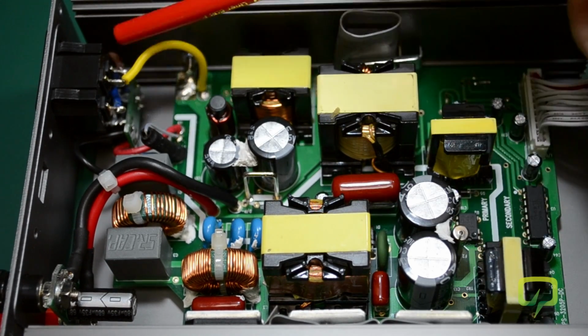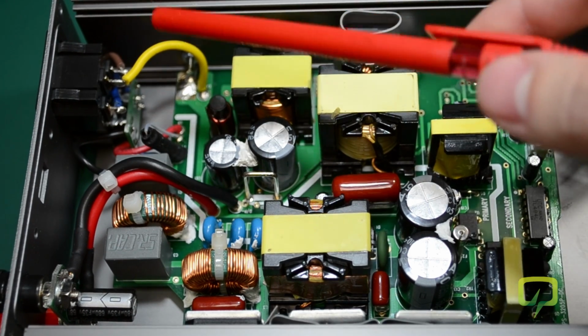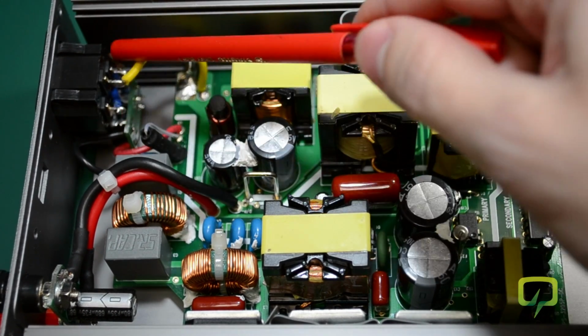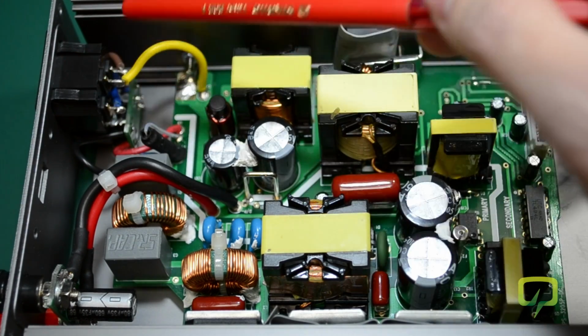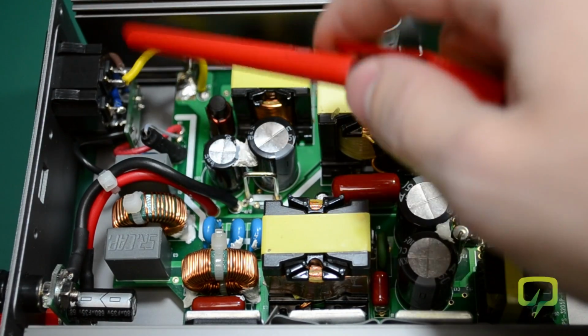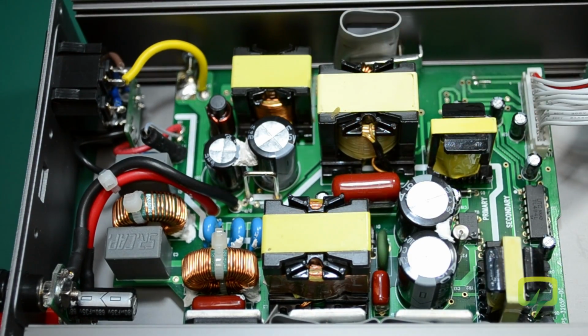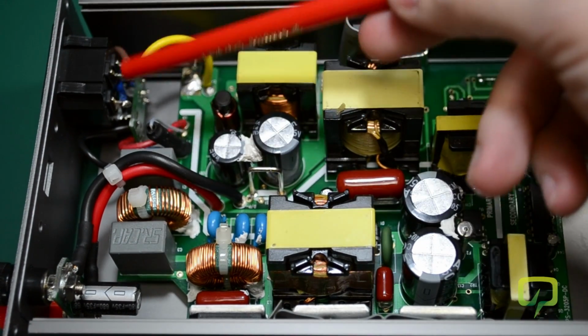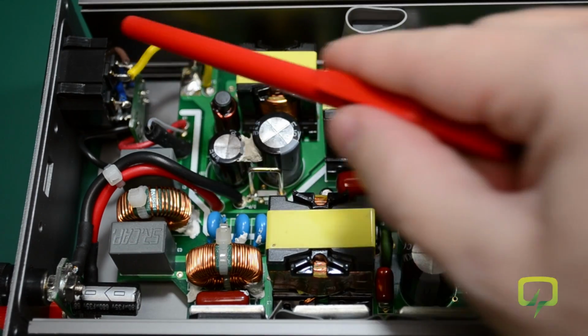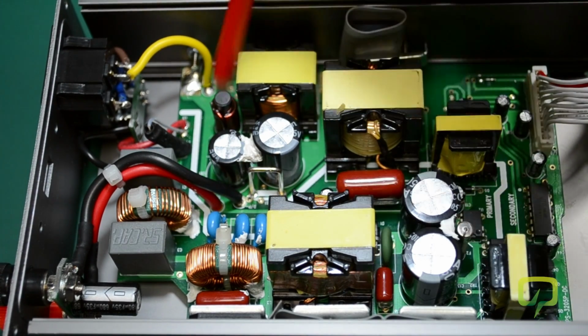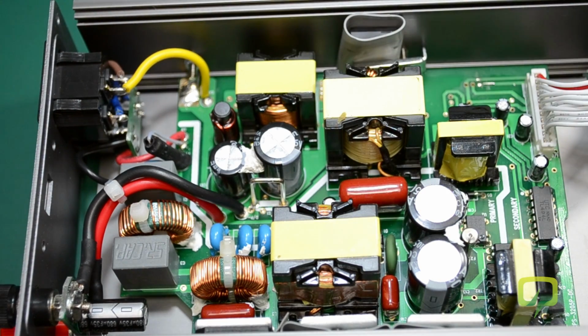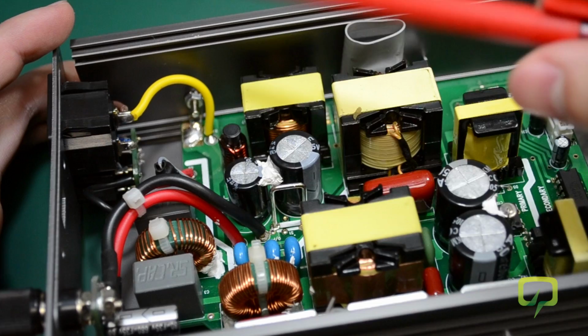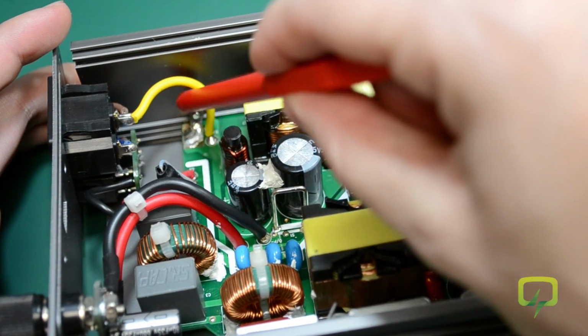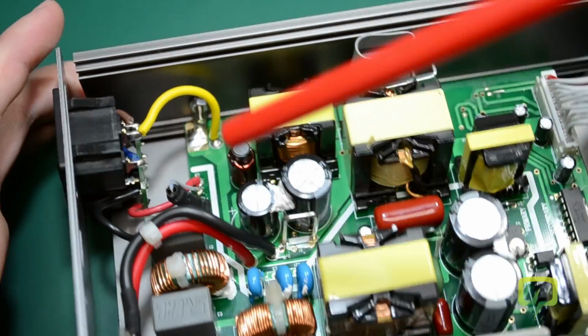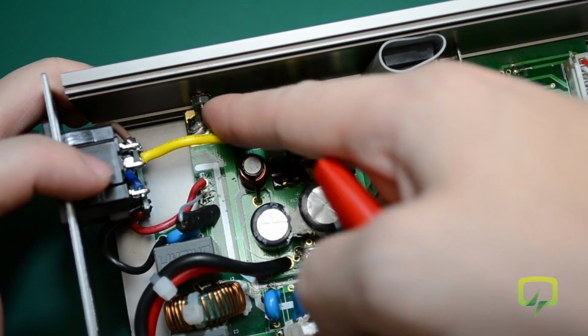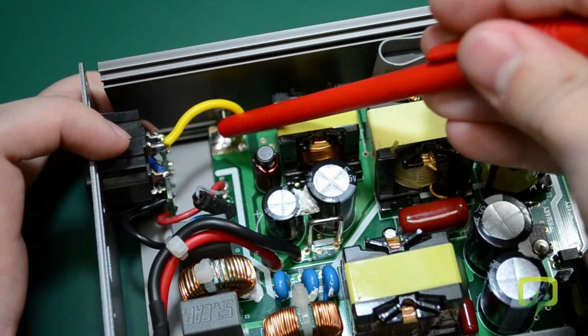Now, starting from the AC input of this power supply, I already see something I don't like. There is no heat shrink on the AC input terminals of the IEC mains socket. It is generally desirable to heat shrink these input terminals to improve the safety of the power supply, but in this case we have no isolation on the input terminals. Moving forward, the earth lug is soldered on the PCB. It looks like a nice solid connection, and the PCB itself has a connecting tab, making the case mains earth referenced. We also have a shake-proof washer in there, so there is no risk of this vibrating loose.